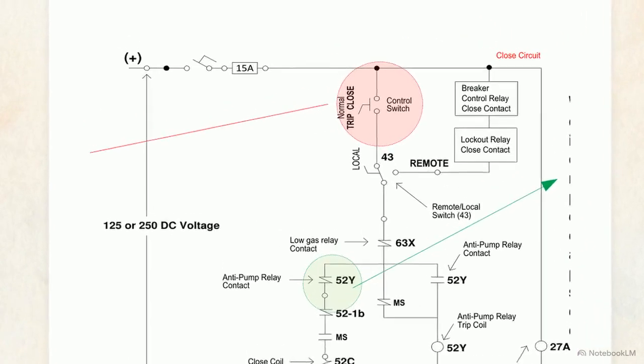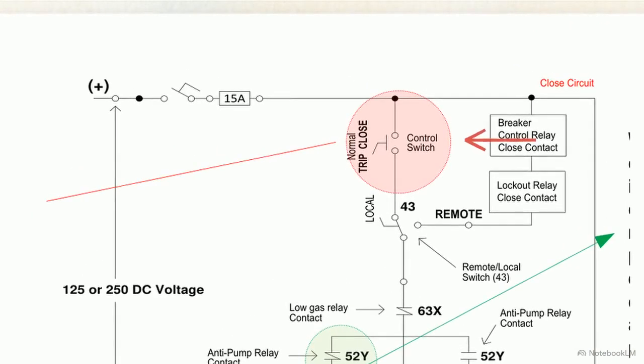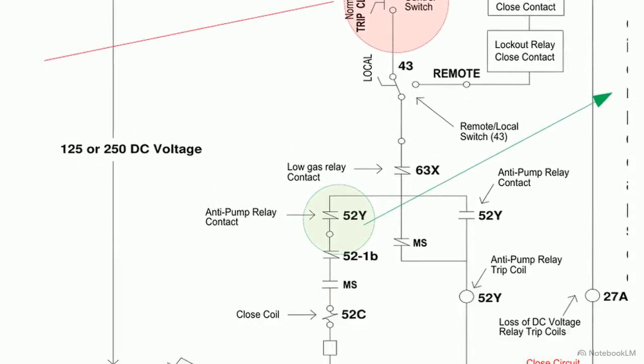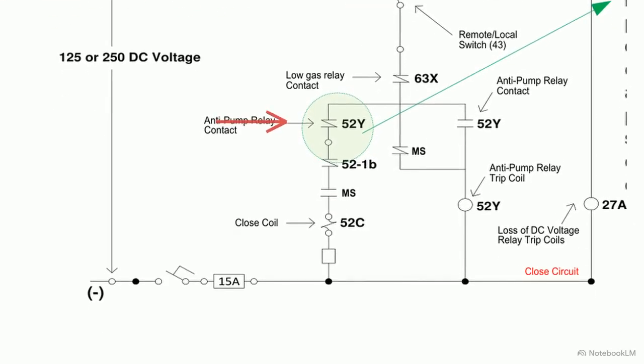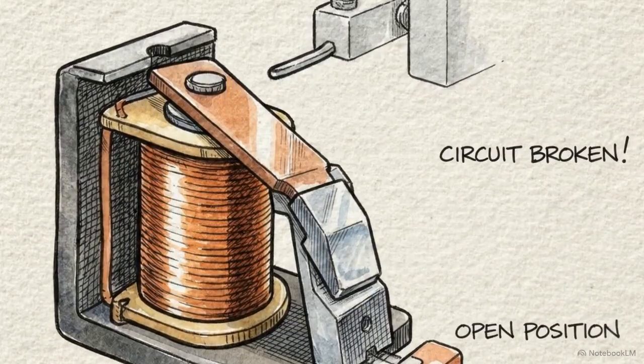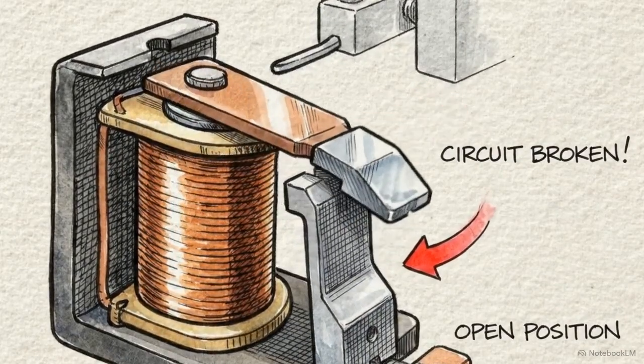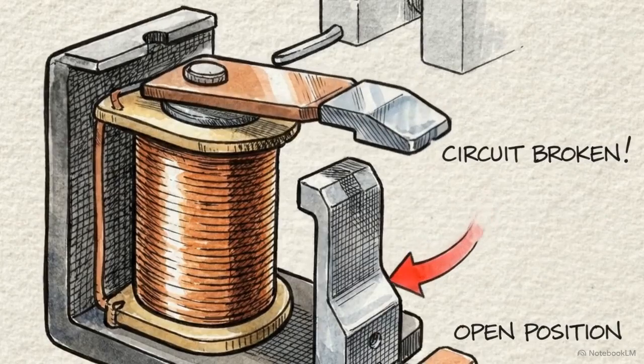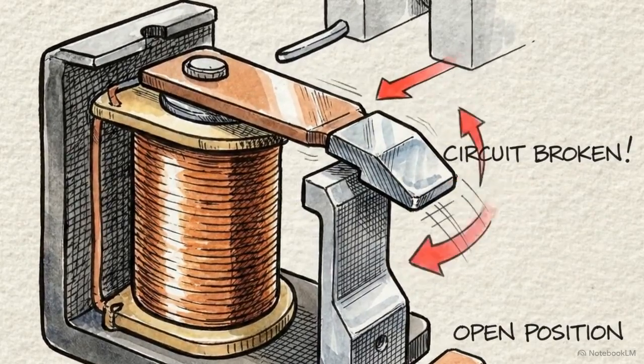We simulate a fault with a sustained close command while a trip signal is active. The 52Y relay energizes, holding the closed circuit open even if the operator command remains active. Validating this crucial physical contact block prevents catastrophic mechanical self-destruction of the switchgear equipment during severe grid emergencies.